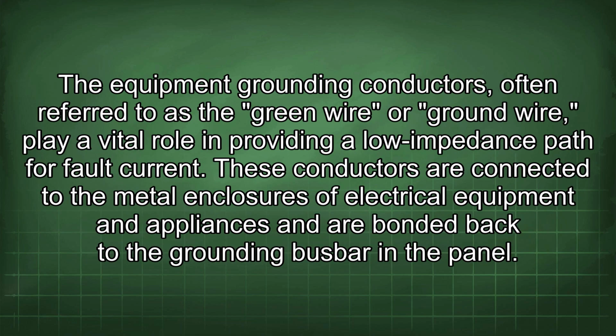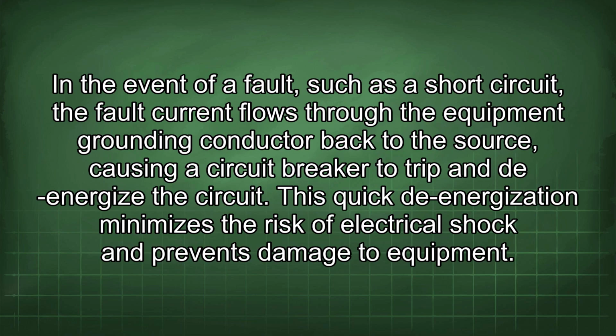The equipment grounding conductors, often referred to as the green wire or ground wire, play a vital role in providing a low-impedance path for fault current. These conductors are connected to the metal enclosures of electrical equipment and appliances and are bonded back to the grounding busbar in the panel. In the event of a fault, such as a short circuit, the fault current flows through the equipment grounding conductor back to the source, causing a circuit breaker to trip and de-energize the circuit. This quick de-energization minimizes the risk of electrical shock and prevents damage to equipment.